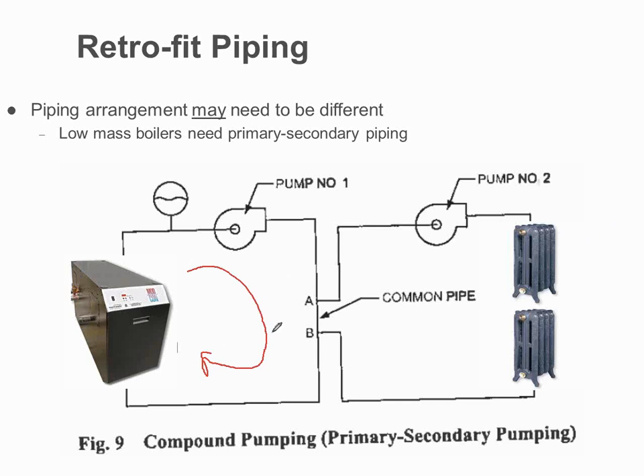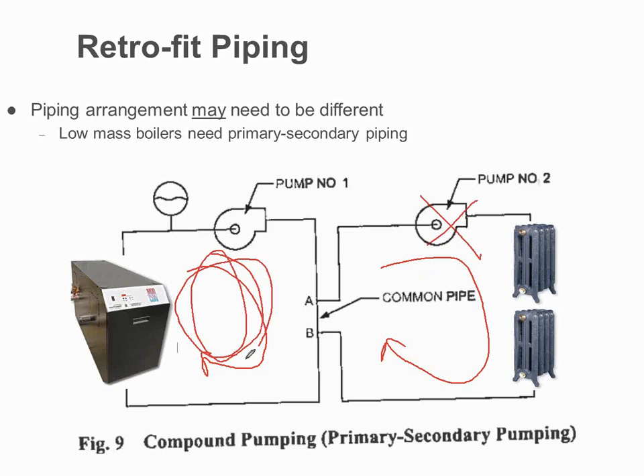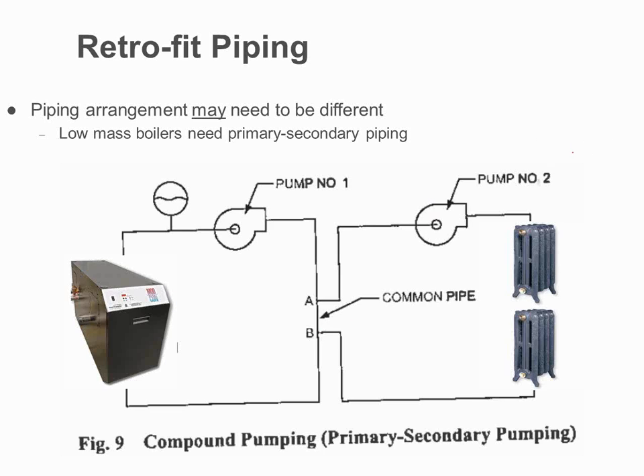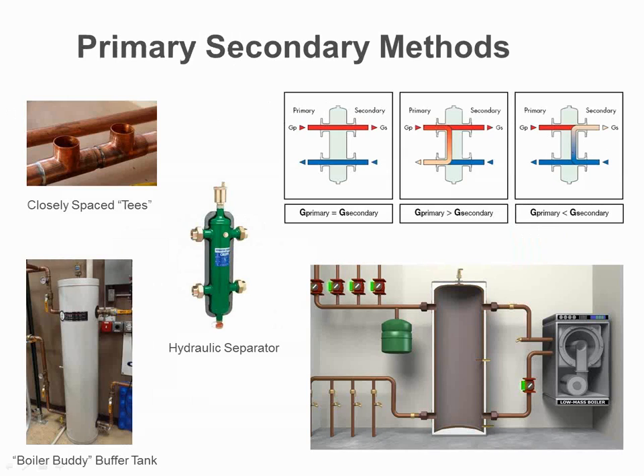So basically pump number 1 in this case is responsible for only the pressure drop of the boiler and the boiler room piping. Pump number 2 is responsible for the pressure drop of the building, and they have absolutely nothing to do with one another. If pump number 2 is off, then all the flow goes to this primary pipe only, just this loop. If pump number 2 actually turns on, then the flow would take this path and make a right-hand turn here and go all the way around this loop. I'm as good of an artist on this computer as I am on a whiteboard. All right, move along.